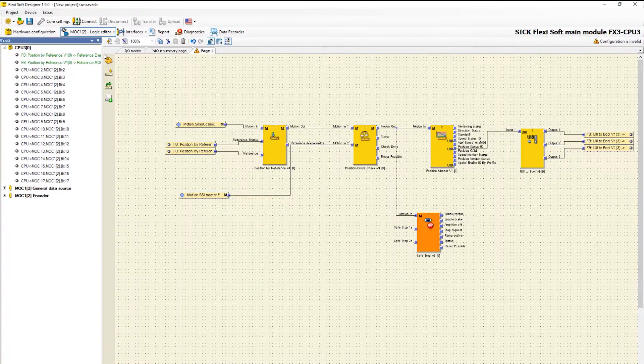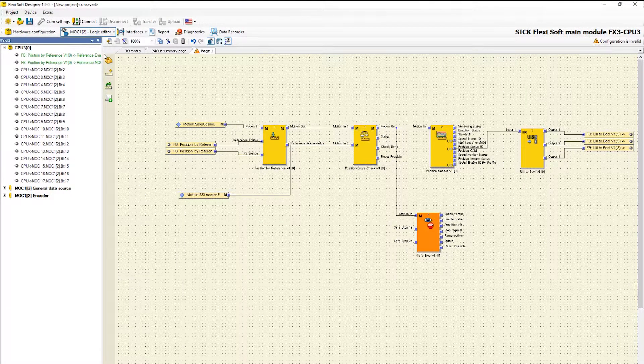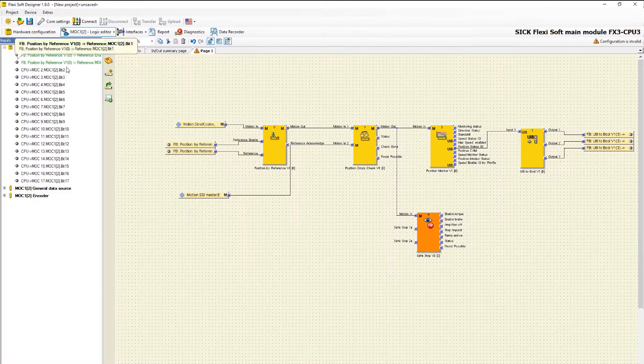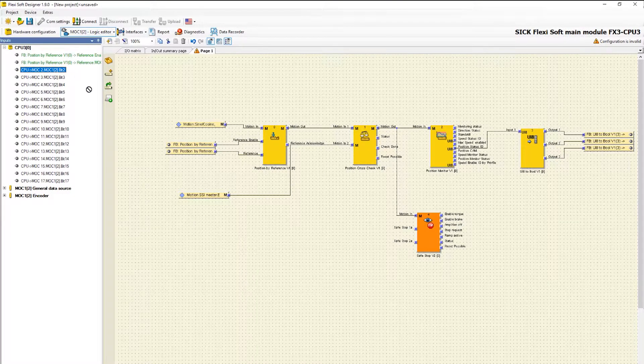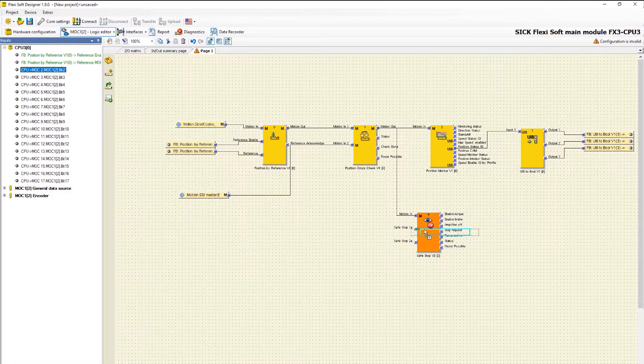After that we switch back to the MOC1 logic. The output bit 2 from the CPU, which is connected to the e-stop, is now available here as input bit 2 in register CPU3 of the tab Inputs. So let's connect the signal of the e-stop to the input Safe Stop 1a.